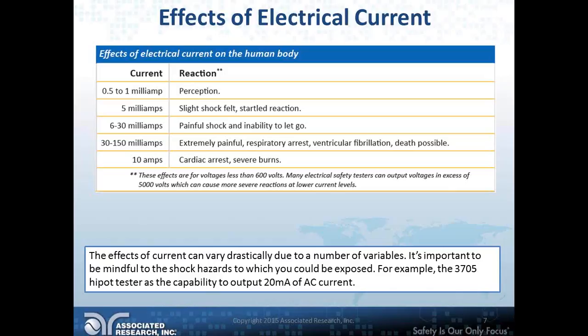Because with most hipot test equipment or dielectric withstand test equipment out there, it will give a voltage value and a current range, the maximum current it can measure up to before the unit trips out and is no longer able to measure. You've basically saturated the instrument, and it'll usually give you some type of message, over current or breakdown or something along those lines. We have equipment that can go up into the 100 milliamp range or higher.